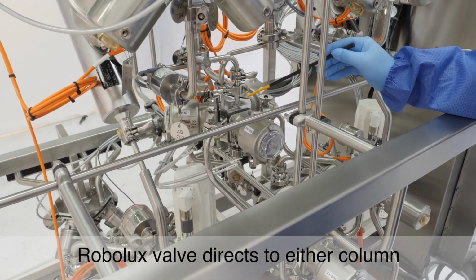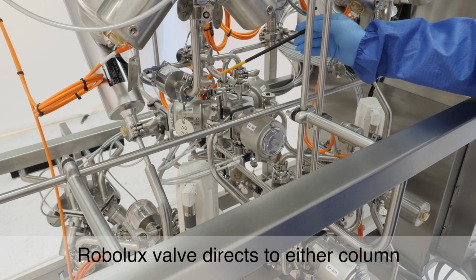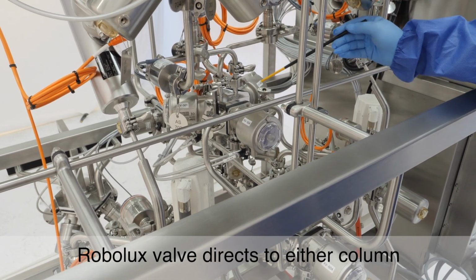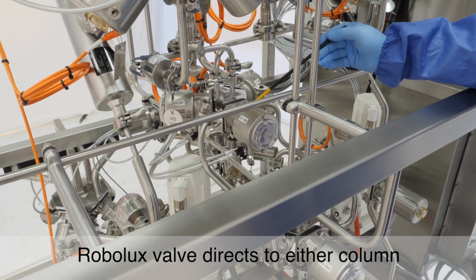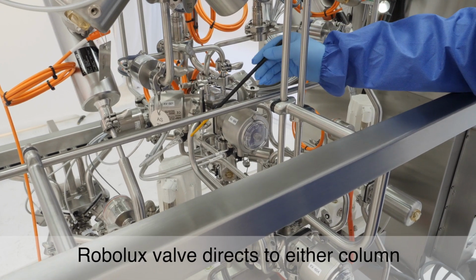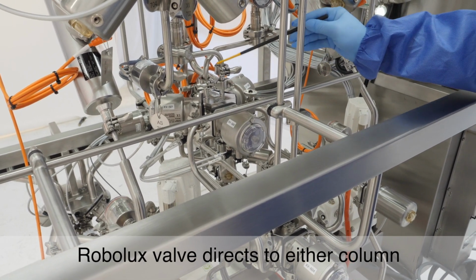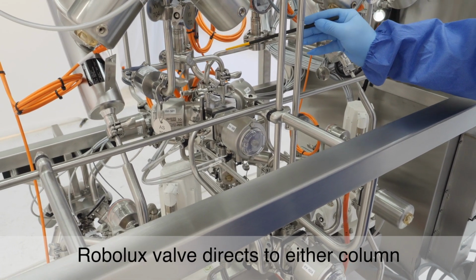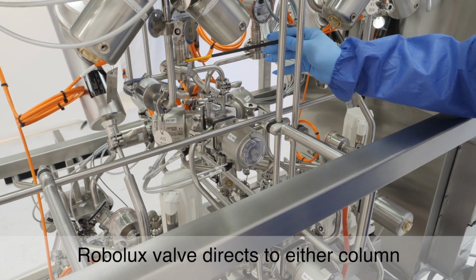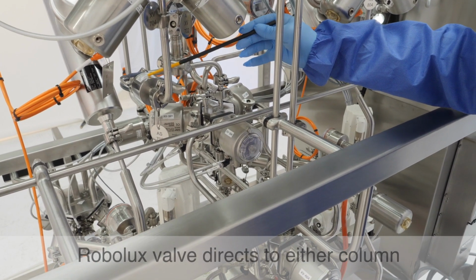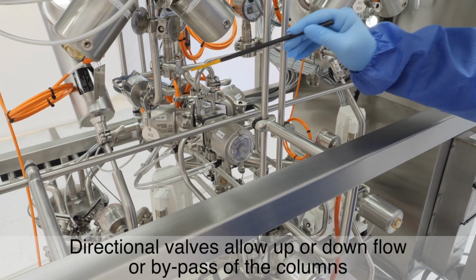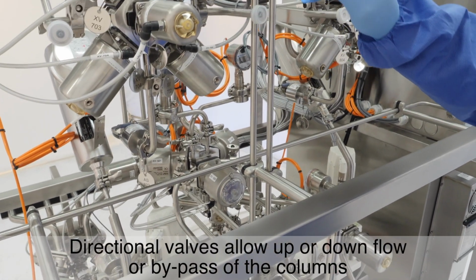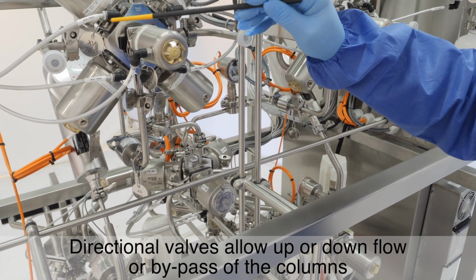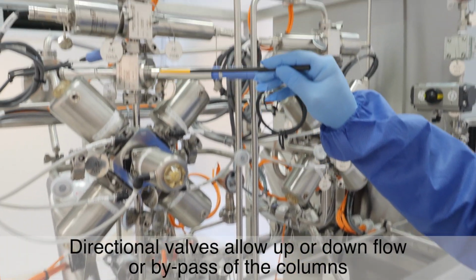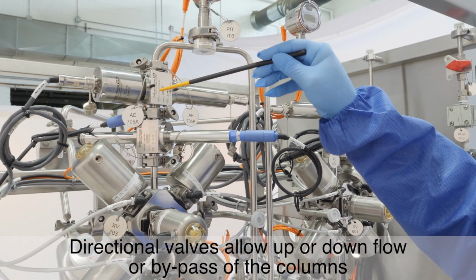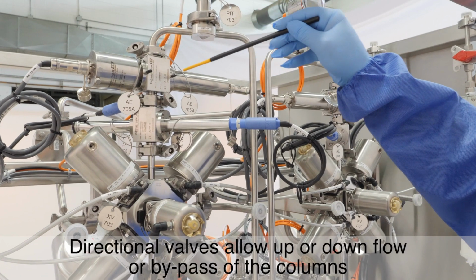Okay, let's take an actual look at this section. The first Robolux valve directs the flows coming from the buffer and feed pumps to either one of the columns, in parallel or in sequence. Here, the flow leaves in the direction of column 1, first passing through the pre-column pressure gauge, an air sensor, and into the directional valve of the column, where column 1 can either be bypassed or the flow directed to the column in an up or down direction.